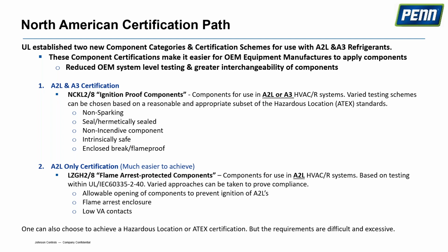This specifically refers to components, which includes controls. To make it easier for any equipment manufacturer using components that could have a source of ignition, since both refrigerants have some degree of flammability, A2Ls are mildly flammable and A3s are highly flammable. What UL is concerned about is making sure the refrigerant doesn't contact the source of ignition. So for any control used in A2L or A3 systems, they've divided this into two categories. The first, for both refrigerants, is a certification called Nickel 2.